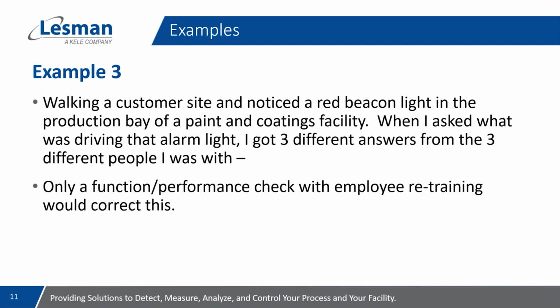Next example is more common than I like to admit. I was walking a site during a project review and I saw a red beacon going off. My nature is to be a little bit curious and nervous, so I asked what the red light meant. As a general rule, red lights in my world don't mean good things. Almost on cue, I got 3 different answers from the 3 people I was with. None of the answers were good things to have happened. One said there was a tank overflow indication, one said it was a high temperature alarm, and the other said it was a gas alarm. Regardless of who had the correct answer, the issue was that none of the operators in the area were paying any attention to the light.